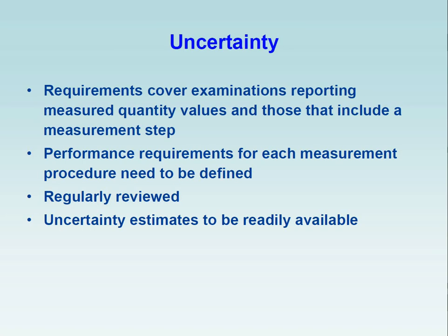Performance requirements for each measurement procedure need to be defined. So you need to state what your performance requirement is, and you need to review regularly. Uncertainty estimates need to be readily available. You don't have to produce those with every single report, but if somebody requests what your uncertainty of measurement is, you should be able to produce it.